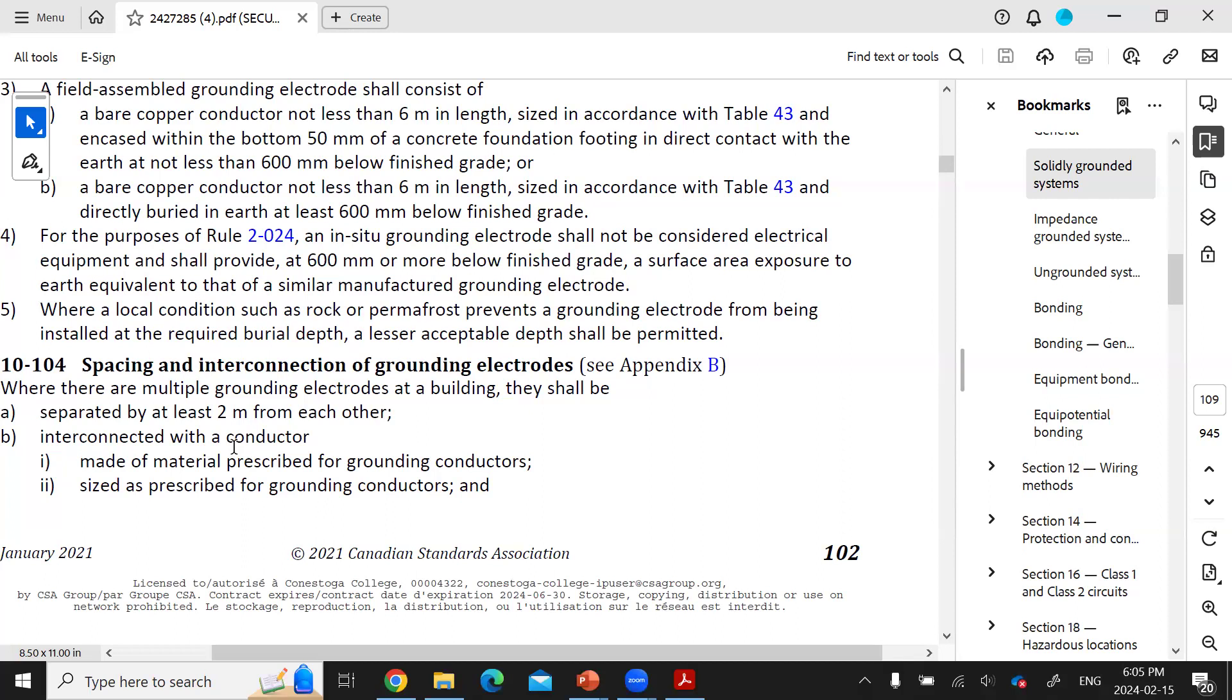If you make those electrodes closer than two meters from one another, there's not going to be enough Earth between those electrodes to provide a low resistance connection to Earth for each rod. And the electrical potential would not fully be discharged into the Earth.